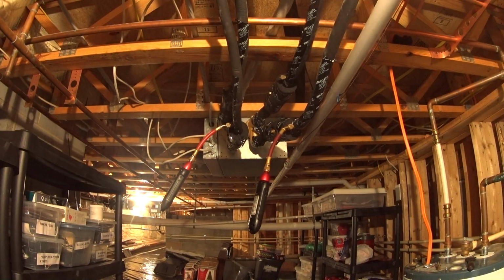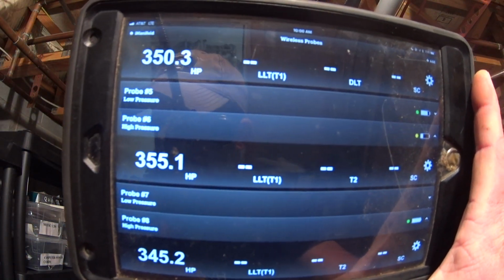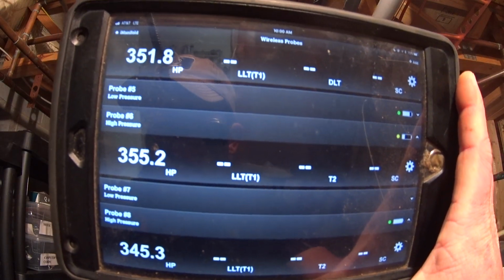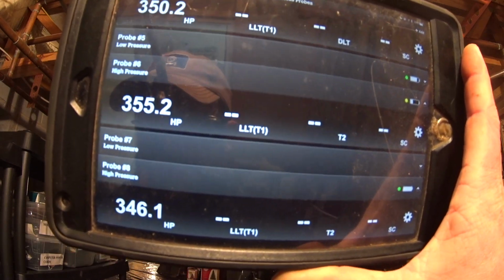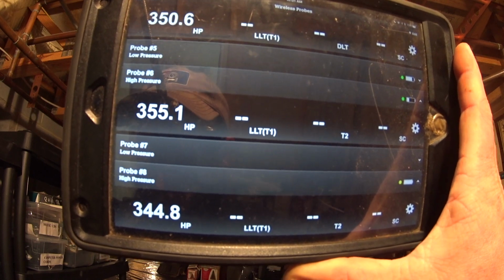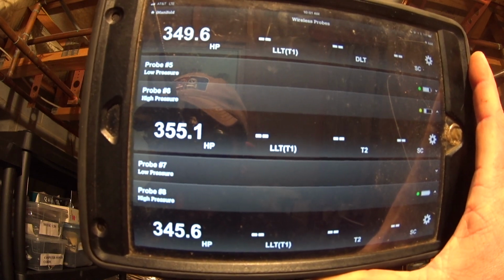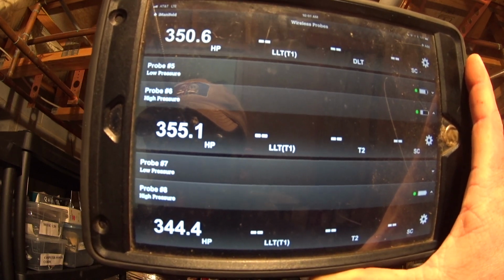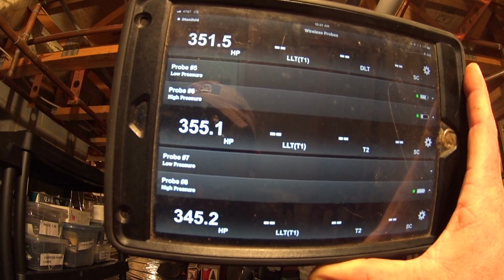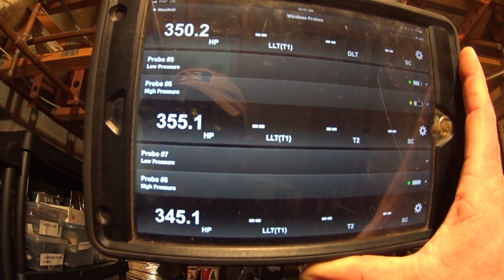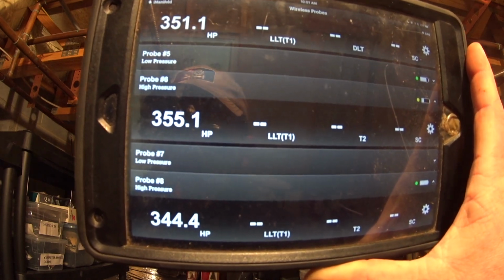It's 9:51. We'll give this one several minutes. We're almost 10 minutes out, and the top one is the overall system, holding at about 350, 355 for the shop unit, and 345 for the bedroom unit that got the significant leak detector spikes. What I'm going to do next is pressurize that bedroom unit to higher pressure, as much as I have left in the tank, to see if I can hear or see the point of leakage at the air handler.